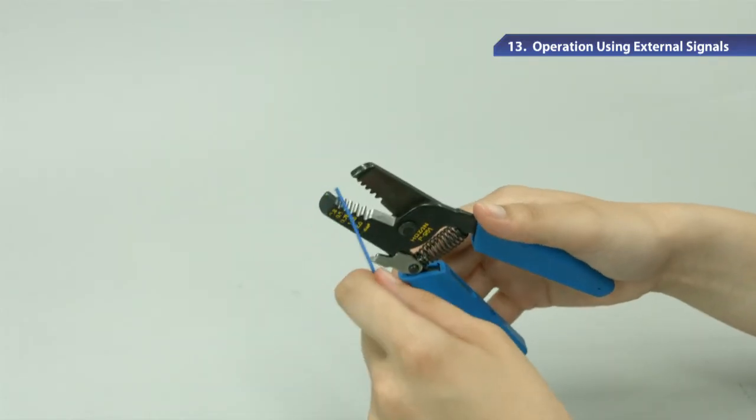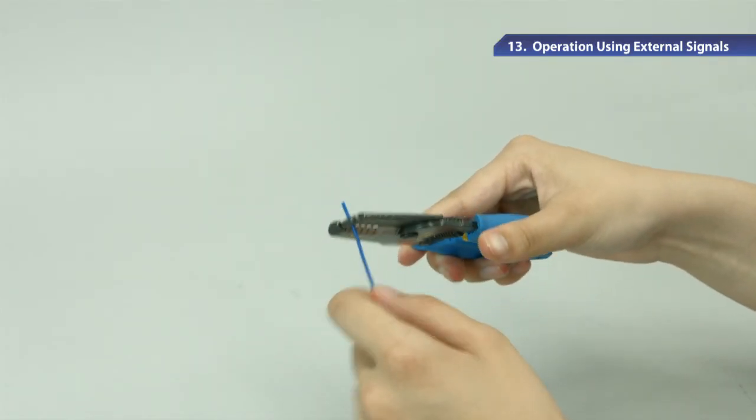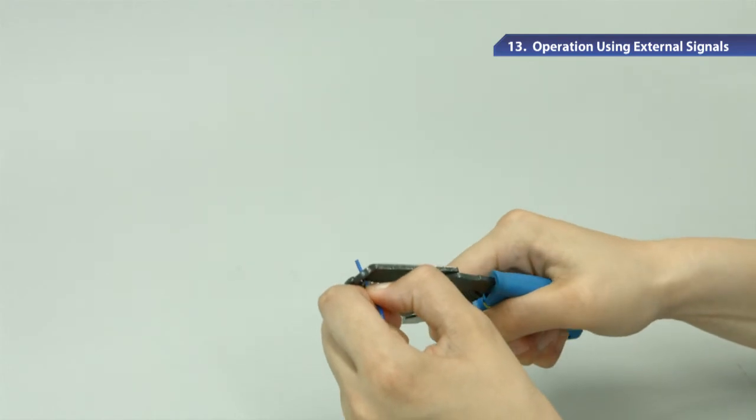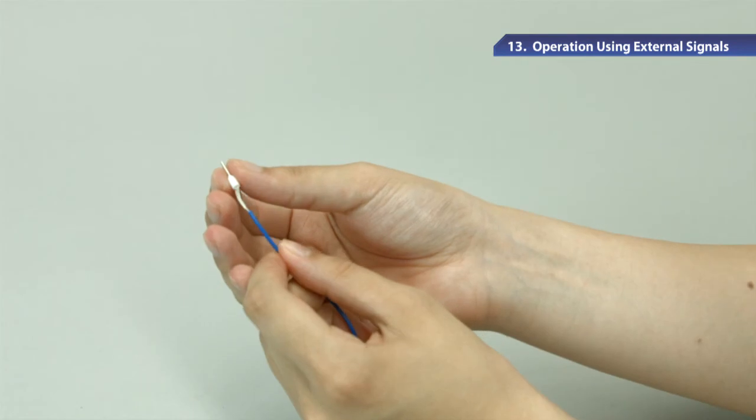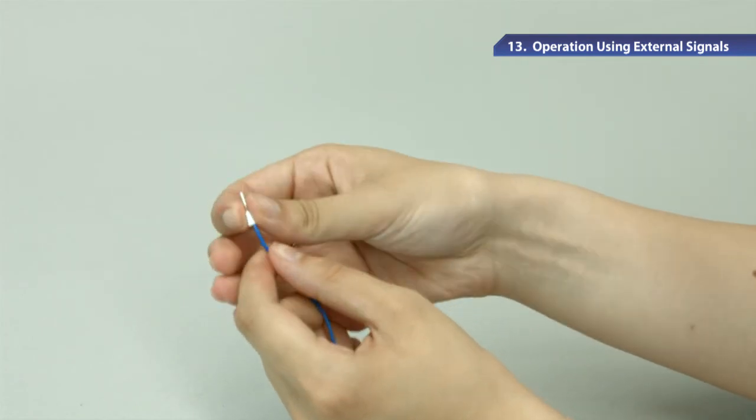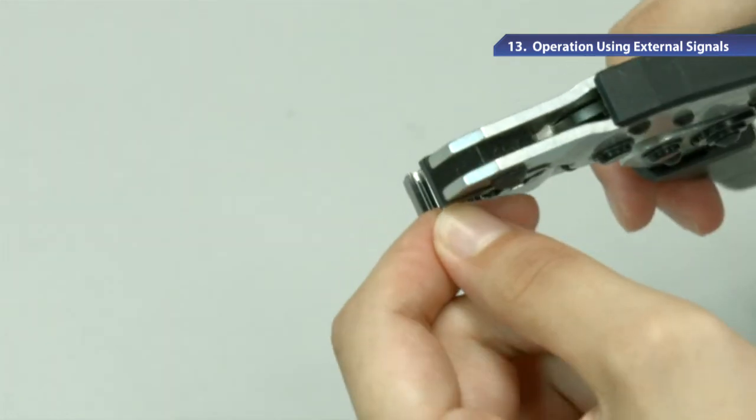Now I'm going to show you how to use the blade terminal. First, strip off about 10mm of the wire at the end. Insert the stripped part of the cable into the terminal and crimp the blade terminal onto the wire with a special tool.